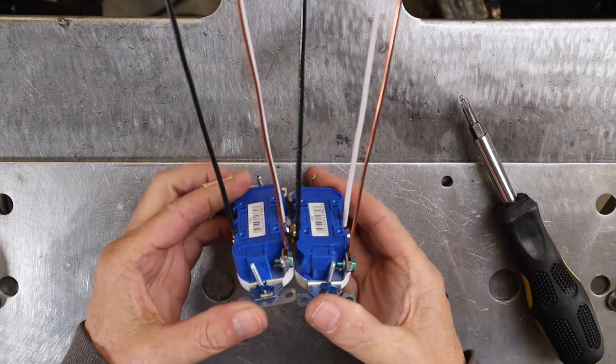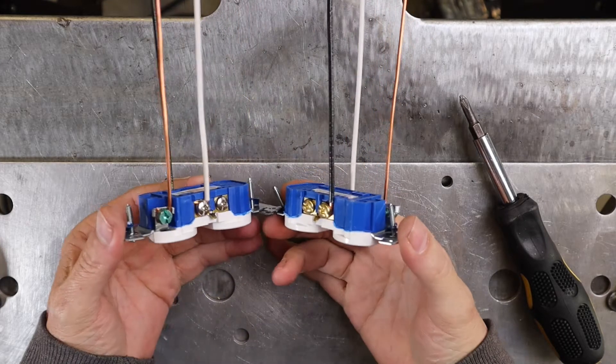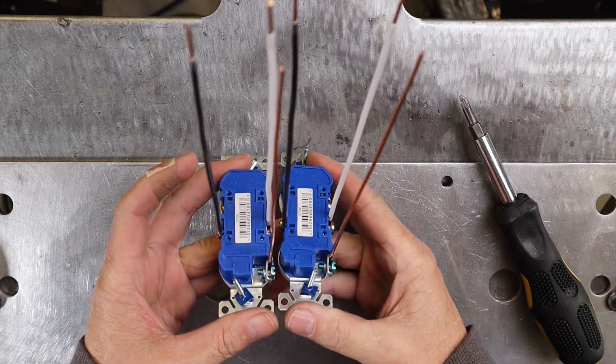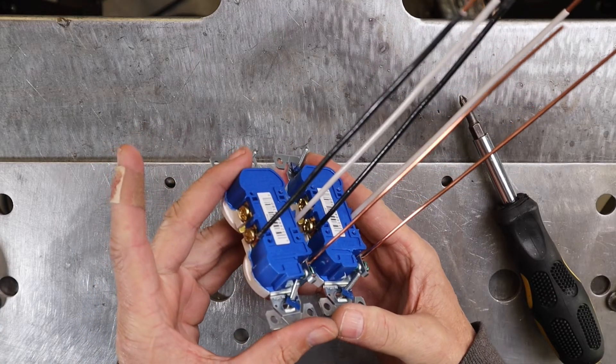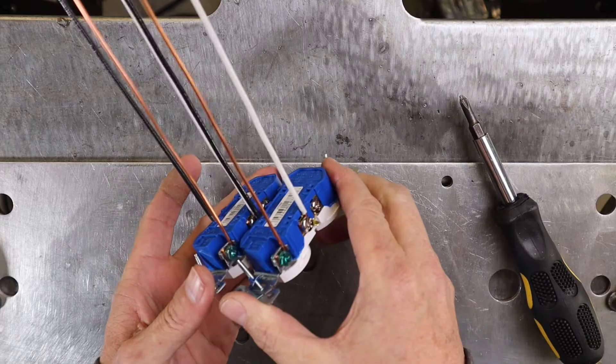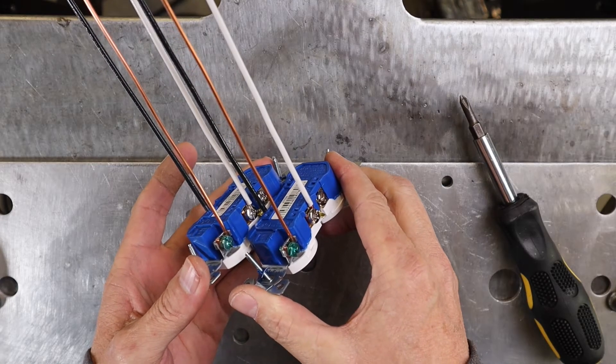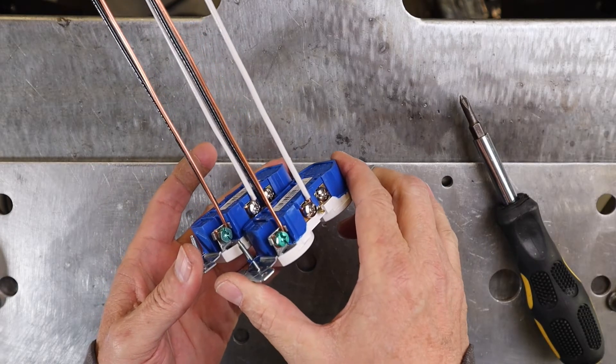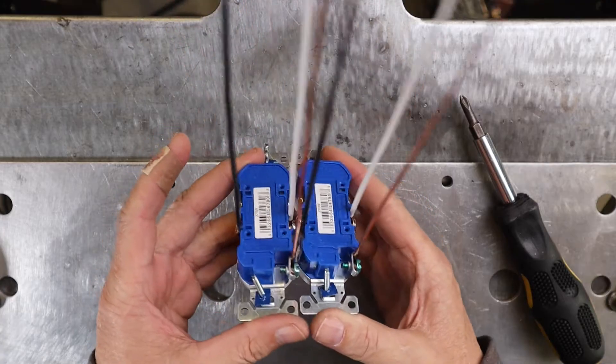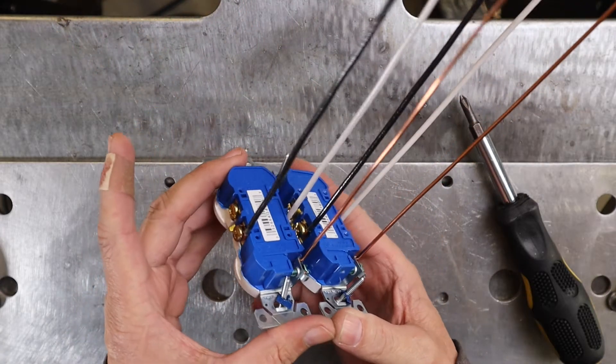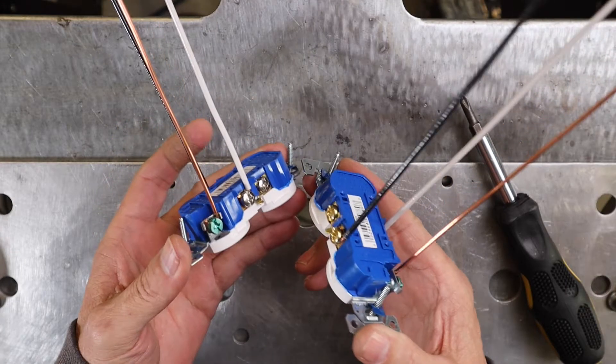Once you get those completed, they'll look like this. And I like to just hold them up side by side and just kind of look at the brass, make sure those are all black. Look at the silver, make sure those are all the white neutrals. And then of course the bare copper on the grounds. Just make sure they're uniform and you've got them all correctly. And unused terminal screws are screwed all the way in.